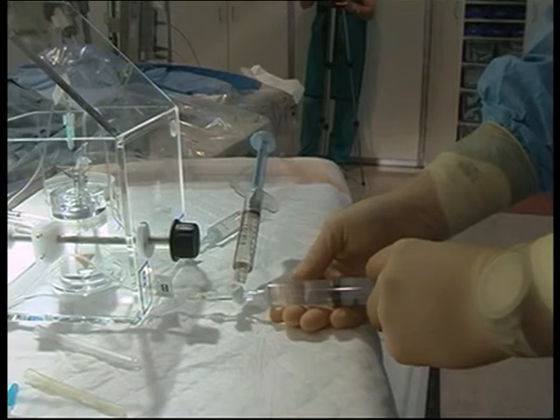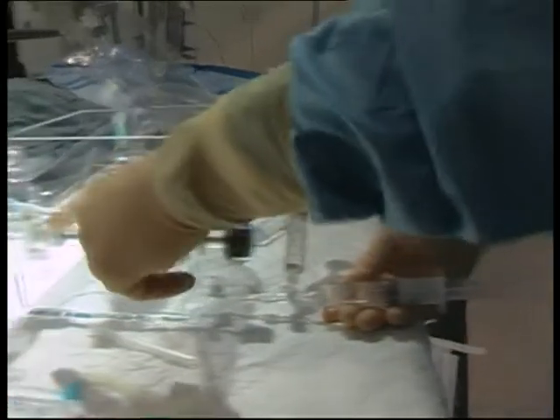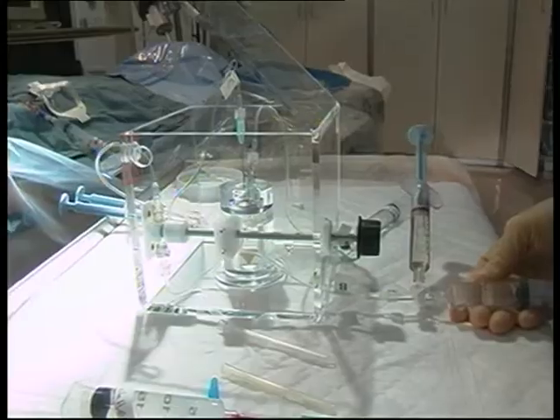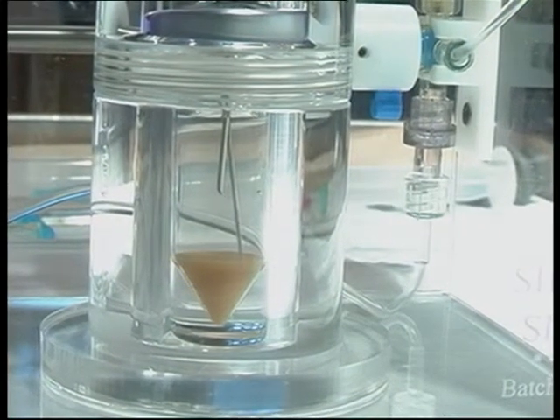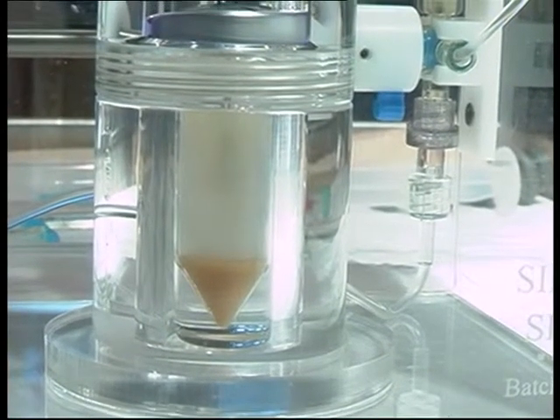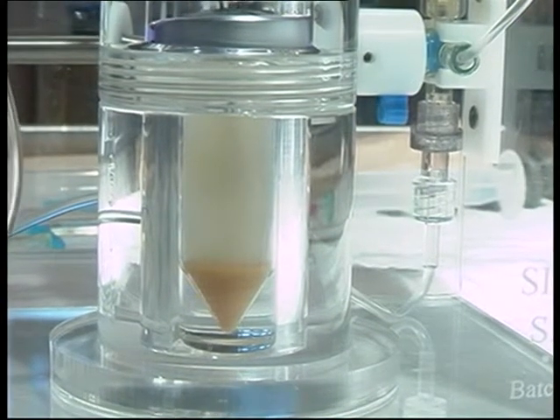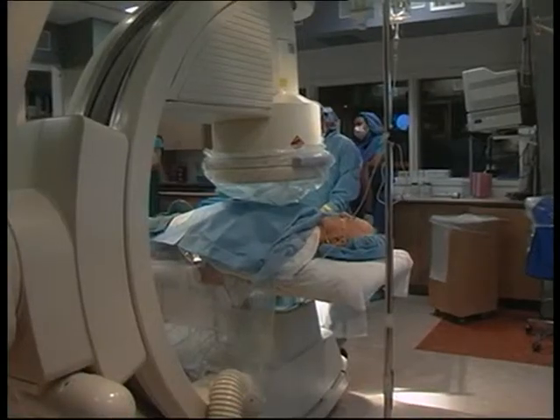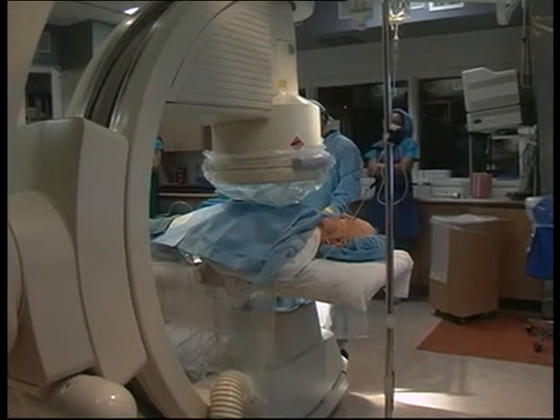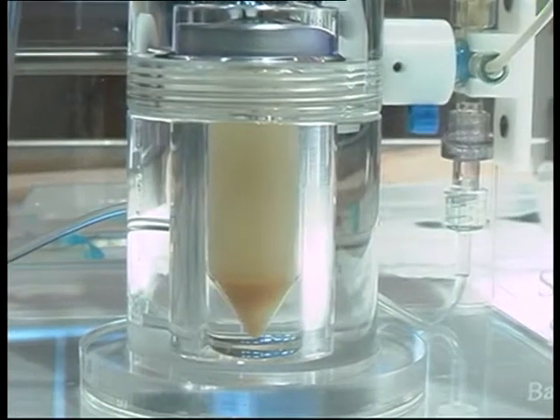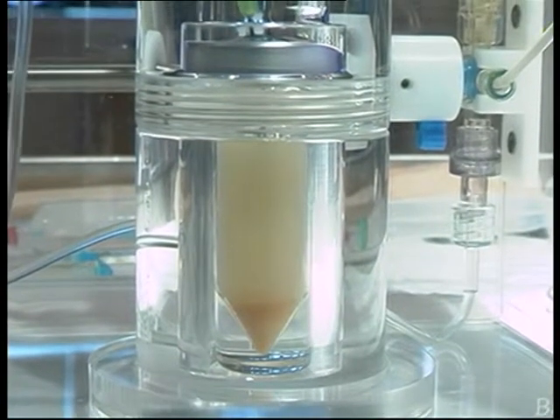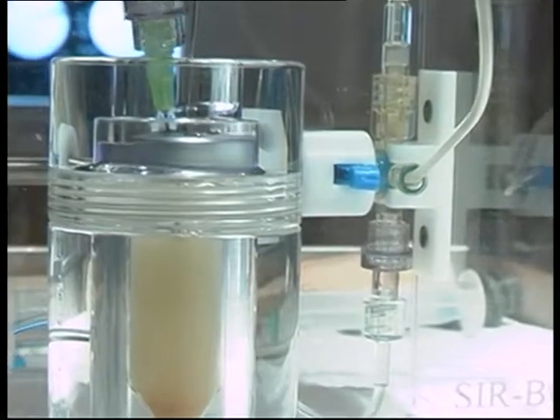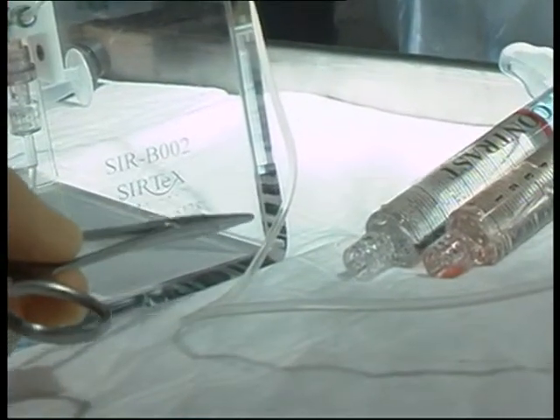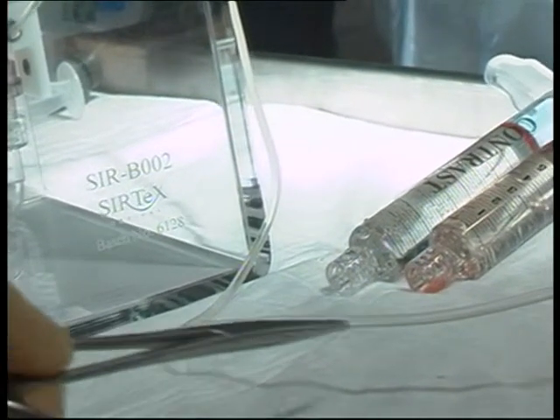There's a series of one-way valves inside of the administration set to prevent any backflow. At this point, we're going to pulse the beads into suspension by injecting water into the inflow line. This is going to load the outflow and delivery catheter with the microspheres. We're now going to turn the administration set off to the beads. The microspheres are now within the line, the outflow line of the delivery system, going into the microcatheter and into the patient's hepatic artery.